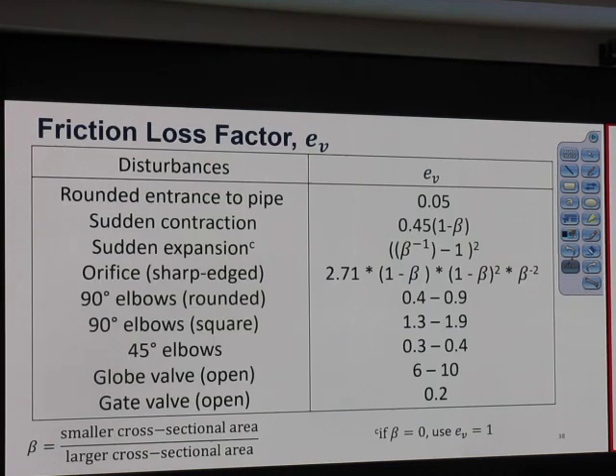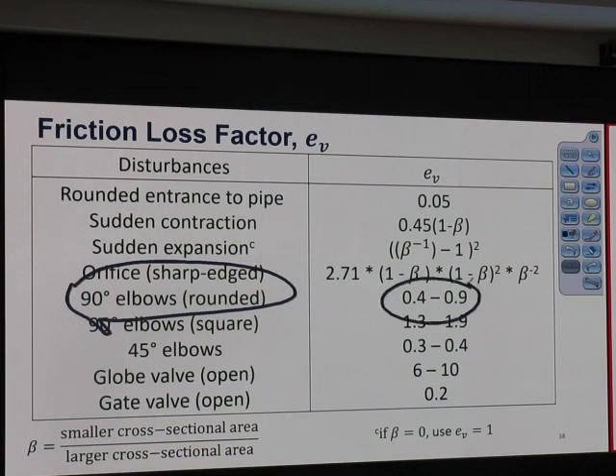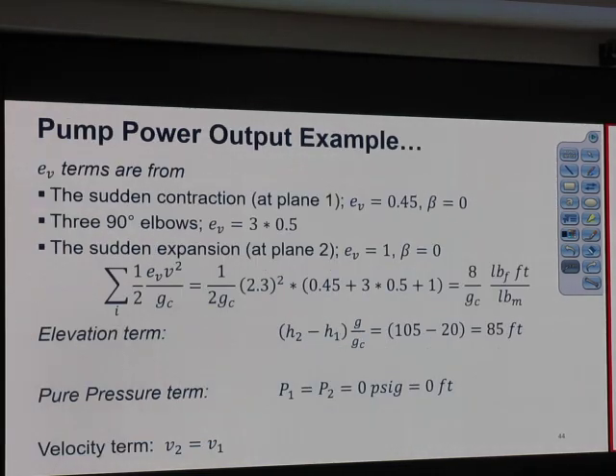Three 90-degree elbows. One, two, three, okay? Each elbow has the friction loss coefficient of 0.5. Where does that 0.5 come from? A table, right? This table. 0.5 90-degree elbows, round, so I use 0.5.